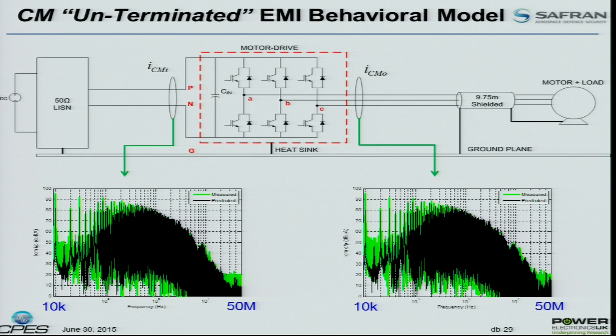So changing the cable, the noise can change, and you can predict it very well. Changing the impedance of your network, the noise can change substantially, and you can predict it well. Putting filters on one side or the other, the predictions still hold. This enables us to look at the system-level issues of the power converters.